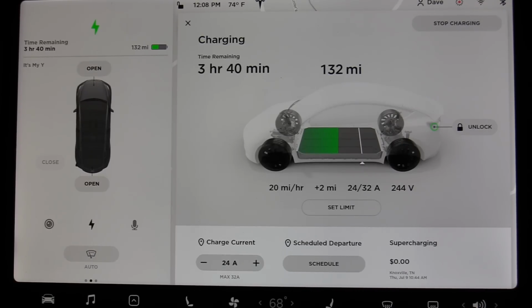This is generally not a problem since you're going to be charging overnight. The last thing you want is to overload the circuit breaker and have it pop open, which would stop your car from charging. So make sure you set your current to whatever the circuit breaker is—if it's a 30 amp circuit breaker, I recommend 80% of that. The circuit will maintain all night long and just keep going.